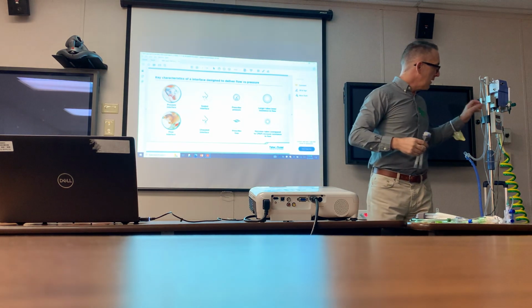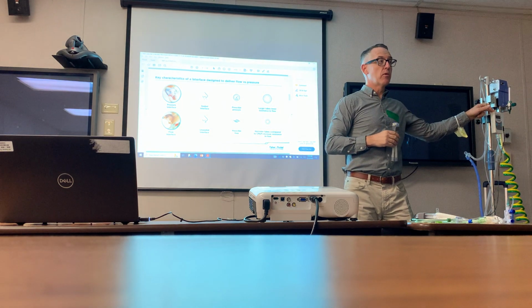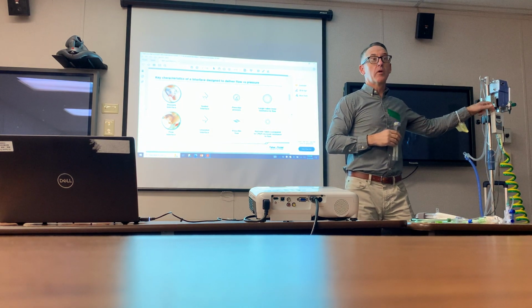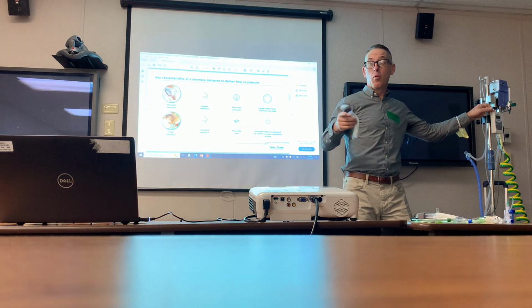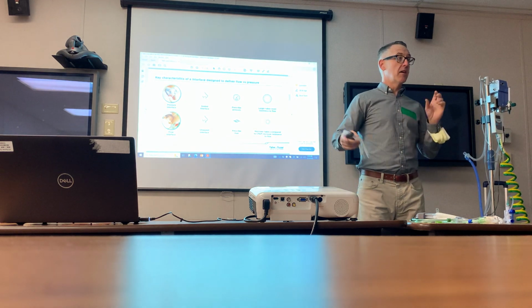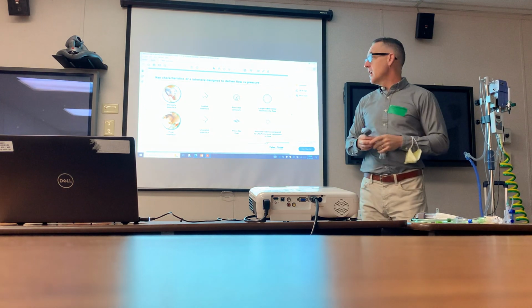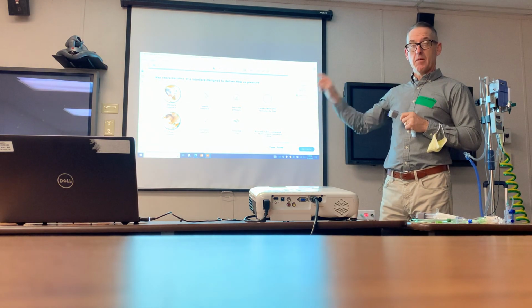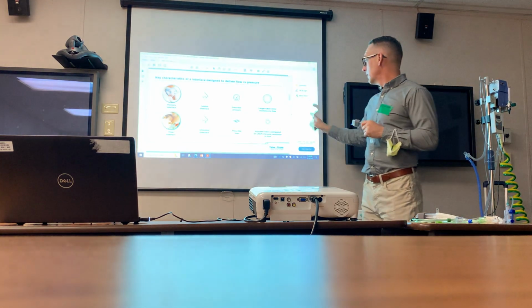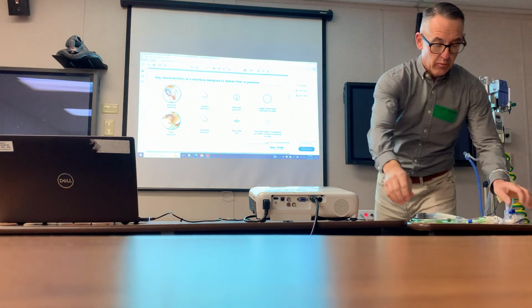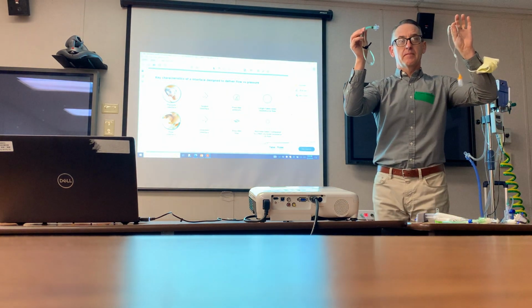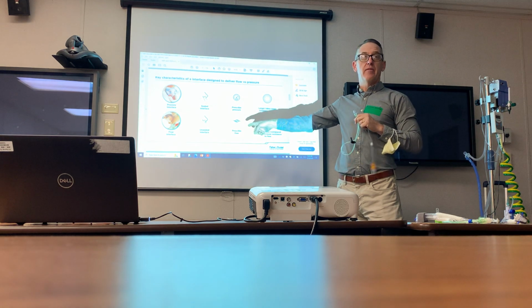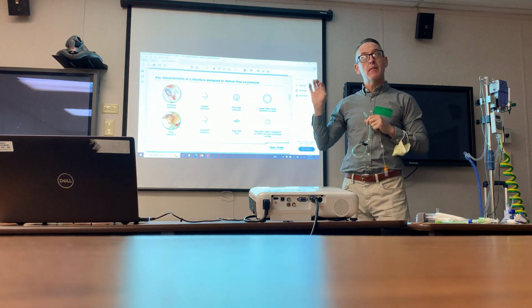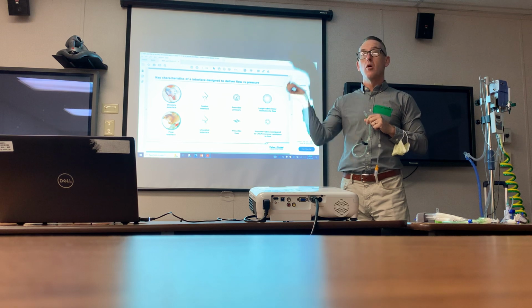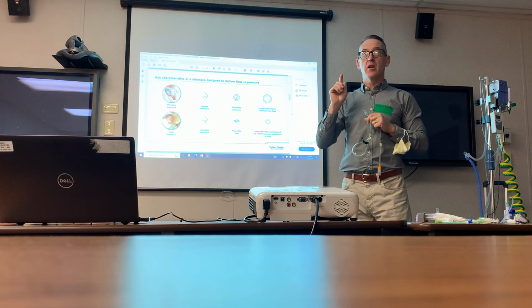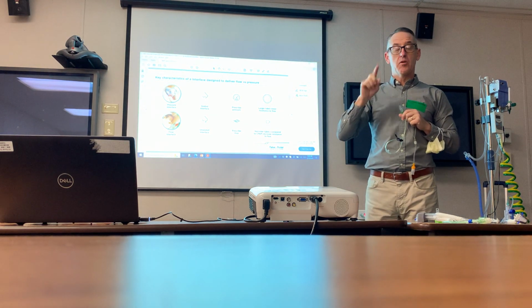I brought with me a bubble CPAP manometer, so when we set up my demo baby, we're going to take a look at that. We're going to measure what it says on the manometer and what it says on the computer. In high flow, we want different criteria: very narrow or restrictive tubing and an unsealed interface. How much? Typically about 50% occlusion or less. There's a reason for that.